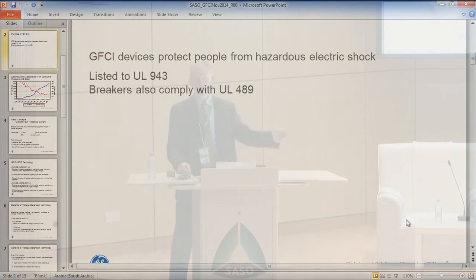That breaker complies with UL 489 from a circuit breaker perspective, and in addition, it complies with UL 943 for shock protection. So all of the requirements of UL 943 with respect to ground fault pickup levels, maximum of 6 milliamps, timing of ground fault interruption, as well as all of the requirements for UL 489, that breaker complies with those requirements. There's an alternative methodology, which is to feed a circuit with a standard circuit breaker and have a ground fault outlet attached to the end of the line. So a normal circuit breaker would provide protection to the wire, and the ground fault circuit receptacle would provide protection to the connected loads.